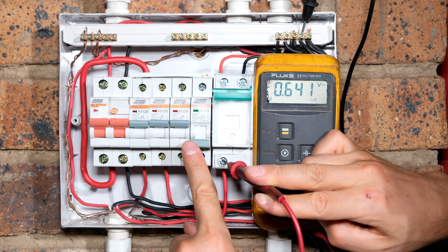That is the reason why we have to have the circuit breaker before the timer, to protect not only the pool pump but also to protect against a fault in the timer. Of course, if I switch this back on, then I will have to manually turn on the timer.